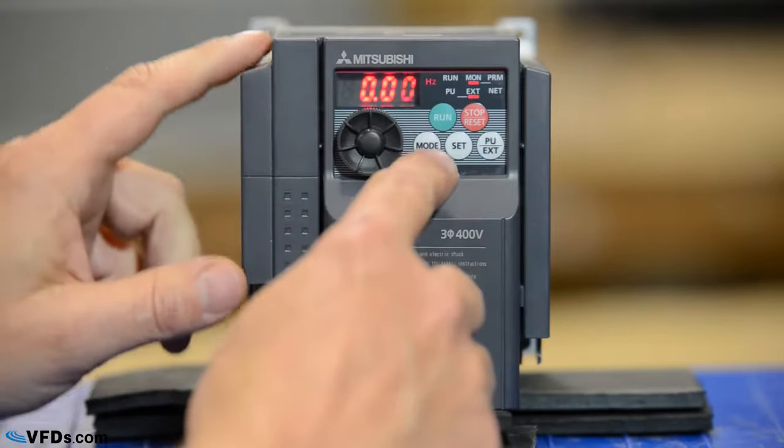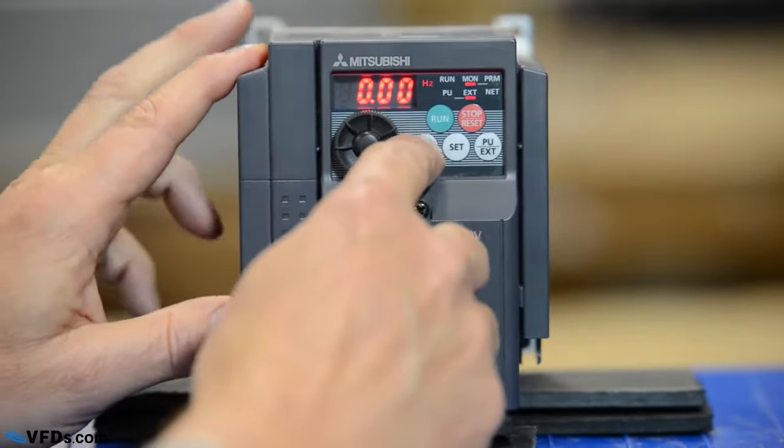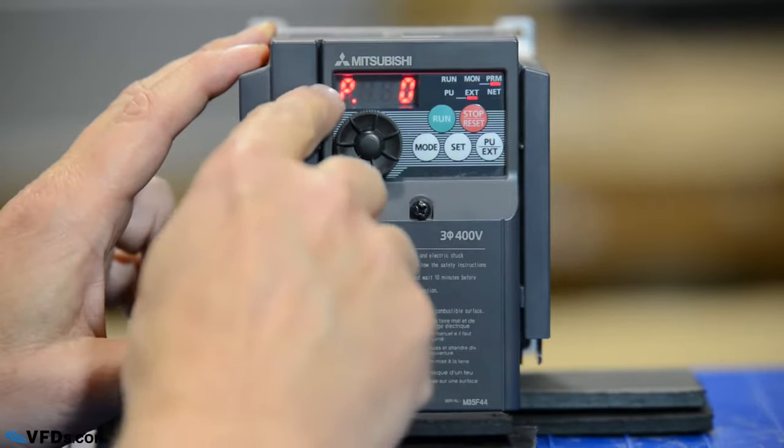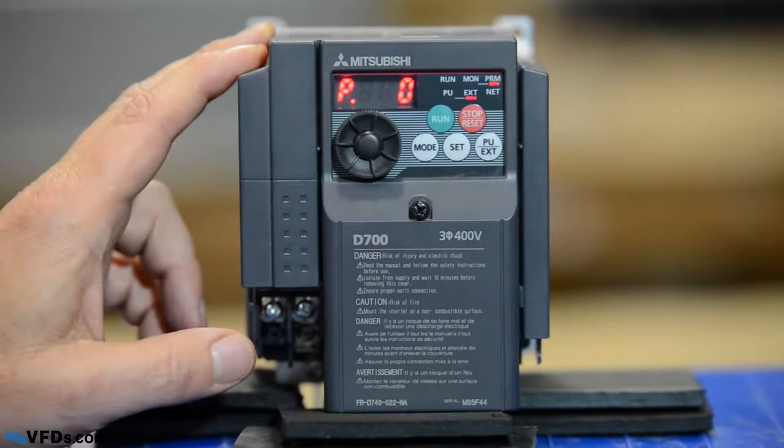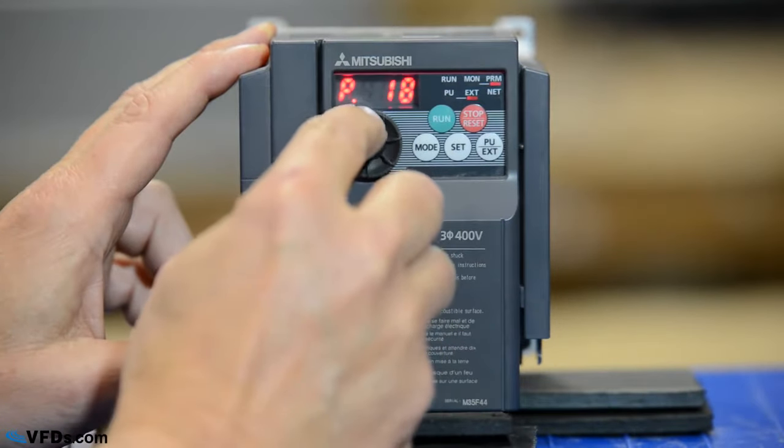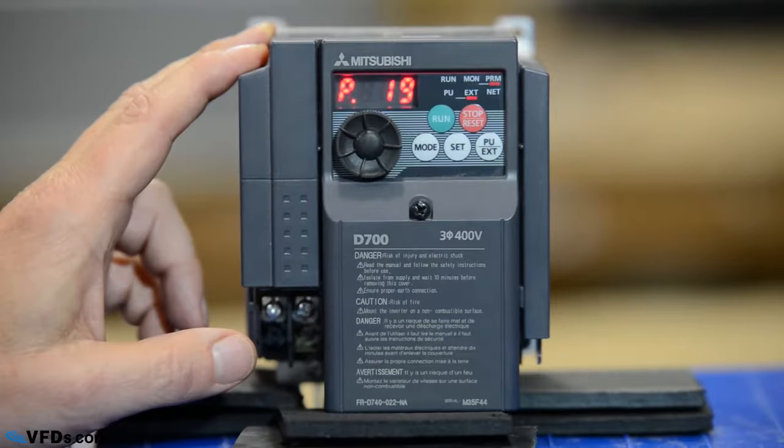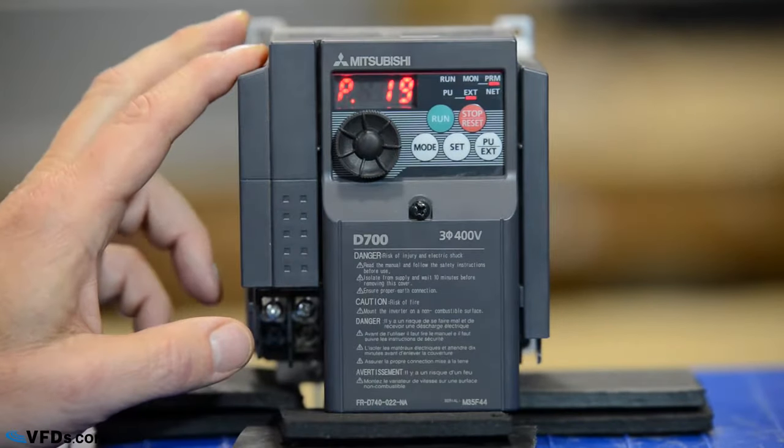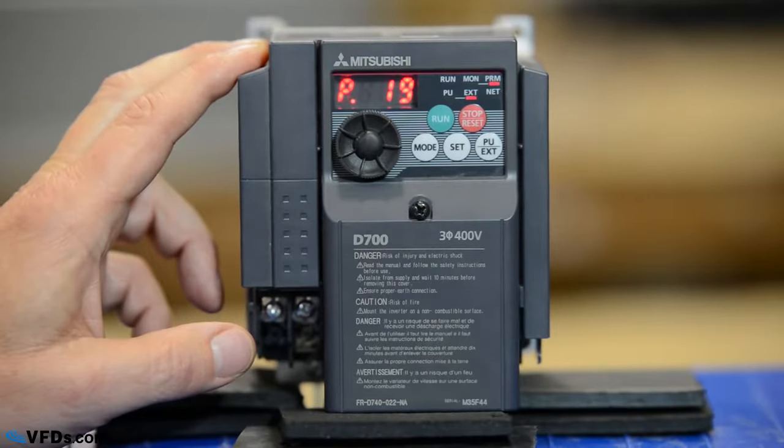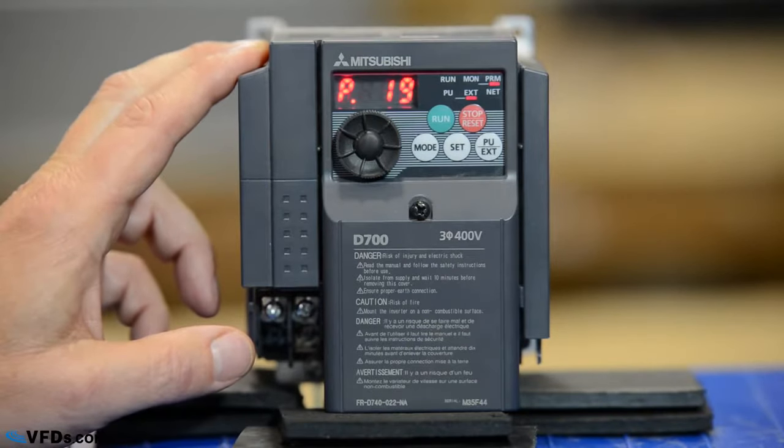We'll first start by pushing the mode button. When we get to the mode button, the first thing we see is P, which stands for parameter. We're going to go to parameter 19 by simply turning the wheel. The first thing I like to program on any drive is the volts and the frequency. These need to match the motor nameplate.